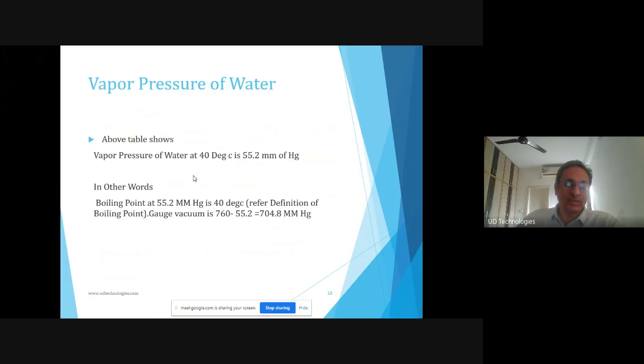Now, how do we see this in industry? There will be gauges everywhere, either a pressure gauge or a vacuum gauge. So how do you convert the gauge vacuum from the absolute pressure? It is 760 minus 55.2, which is 704.8.